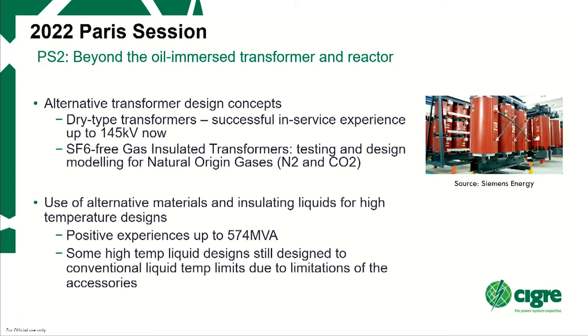Preferential subject 2 was beyond the oil immersed transformer and reactor, with discussion on alternative transformer design concepts. There's been successful in-service experience with dry type transformers up to about 145 kV, and some work in SF6-free gas insulated transformers in testing and design modelling using natural origin gases mainly consisting of nitrogen and carbon dioxide at high pressures.